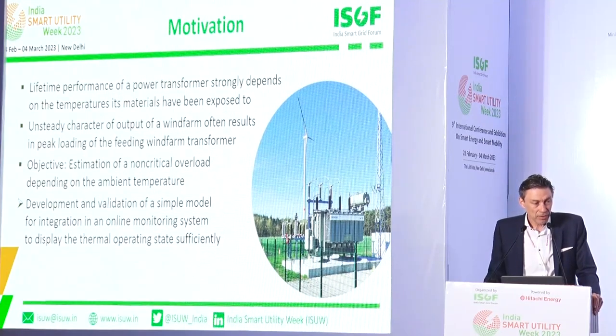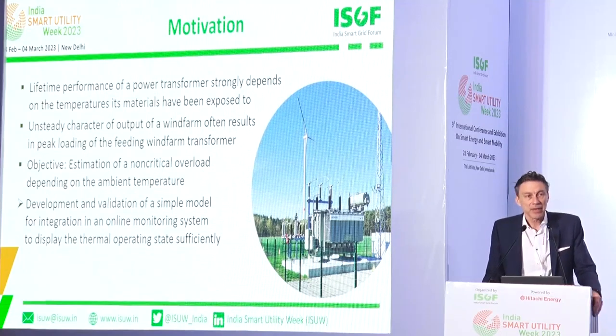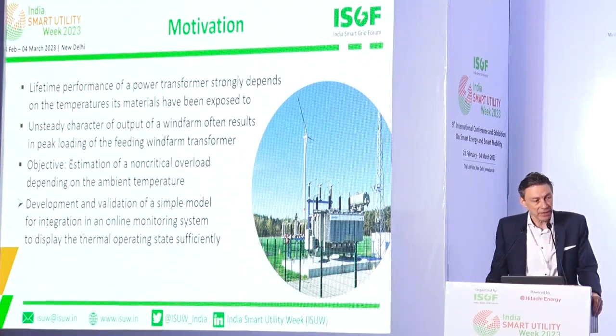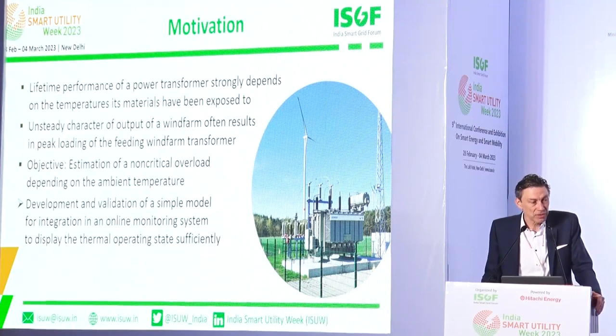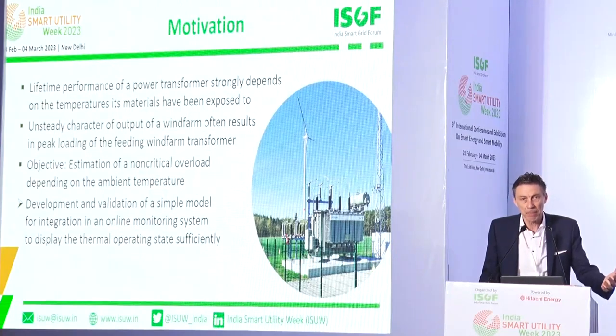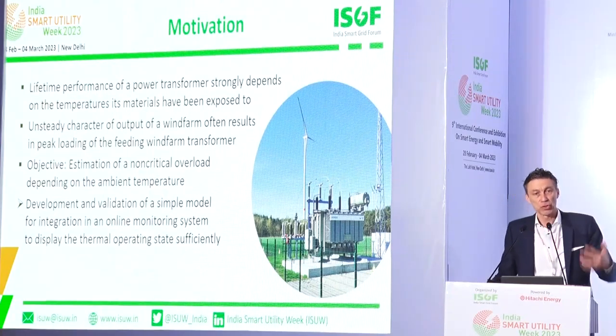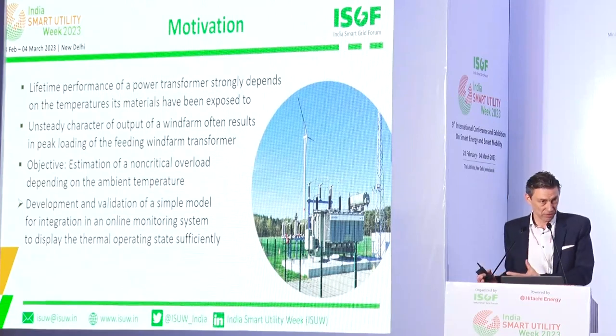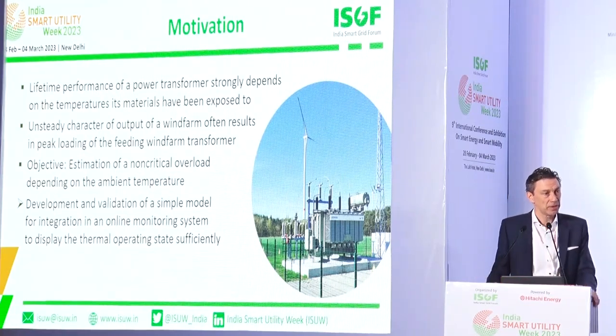The wind has an unsteady character, so the output of a wind farm often results in peak loading of the feeding wind farm transformer, and sometimes these transformers can even be overloaded. So the objective is to estimate a non-critical overload dependent on the ambient temperature.